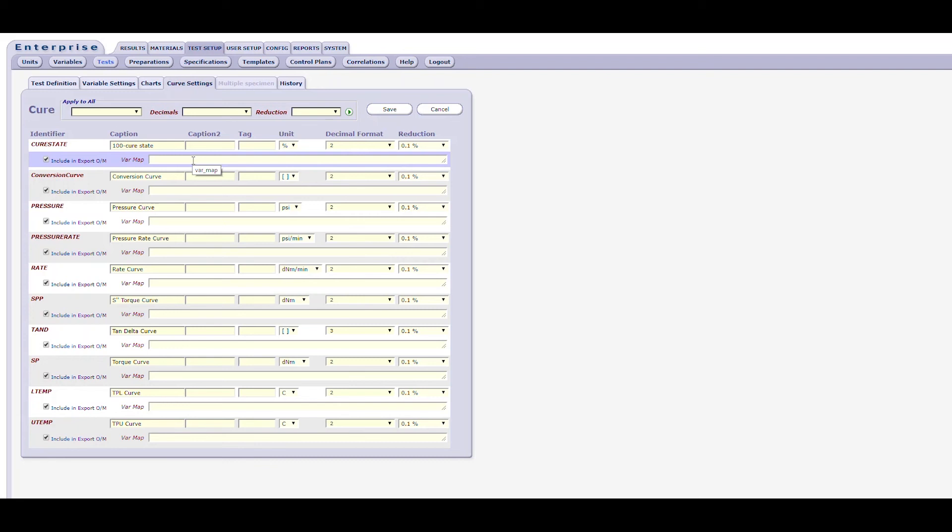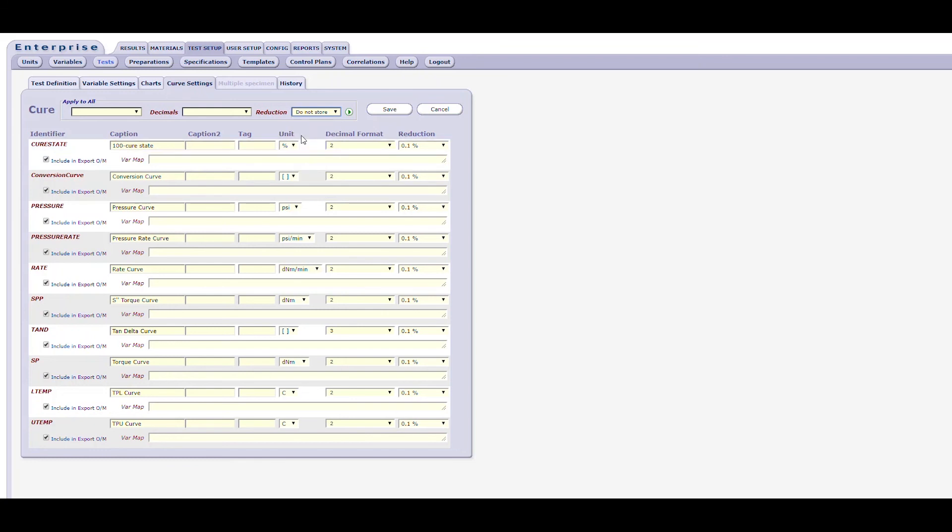Finally, there's a drop-down menu for reduction. This allows you to compress or remove entirely the data stored in the database to each curve in the test. The system saves curve data to the database to allow for it to recalculate the data. You can turn this off by selecting Do Not Store from the reduction drop-down. The other selections range from None to 10%. The amount of reduction that will be appropriate for a given curve depends on the number of data points selected during the test. An algorithm is applied that will compare a set of three data points looking for those that can be removed without greatly changing the state of the curve. Note that some reductions may occur automatically in the wrong test, and the system is designed to prevent memory issues from collecting too many points of the data.